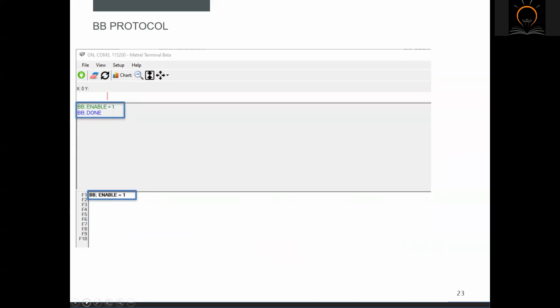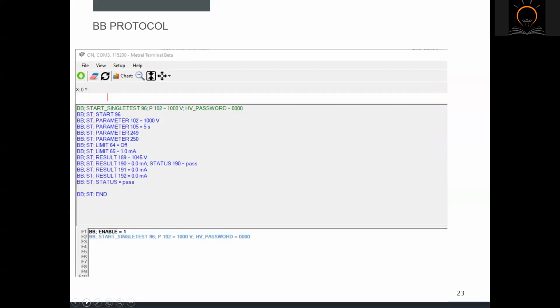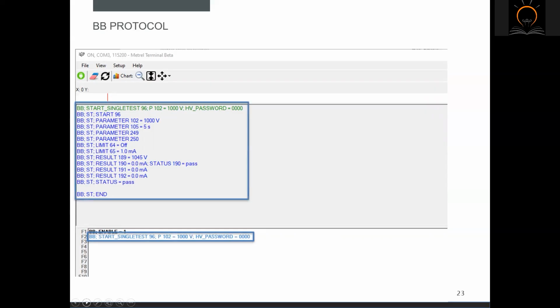In the next step, we will send the string bb start single test 96, which will execute the measurement using ID number 96. In our case, this is a high voltage measurement. The instrument executes the measurement and returns the answer. In our case, these are parameters, limits, results, and status. If needed, it can be set using an extra command that the instrument also returns all intermediate results of the specific measurement.